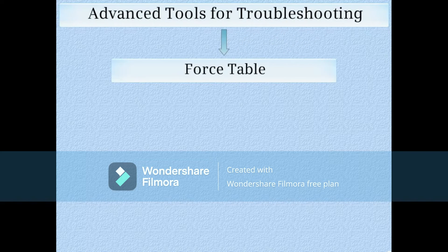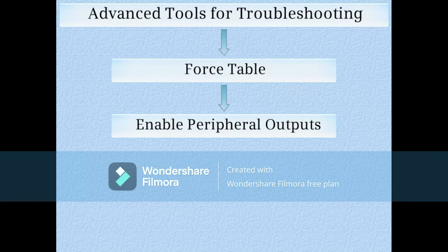While online, double-click a station to bring up its module information tool. Some advanced tools for troubleshooting include the force table, which allows you to overwrite input or output values regardless of their real-world state; enabling peripheral outputs, which allows you to communicate with outputs even if the CPU is in stop mode; a breakpoint toolbar where you can set breakpoints and monitor code stepwise; and statement lists, also called STL. There are videos which show in detail how to use all of the tools mentioned in this video. This concludes the introduction to errors.